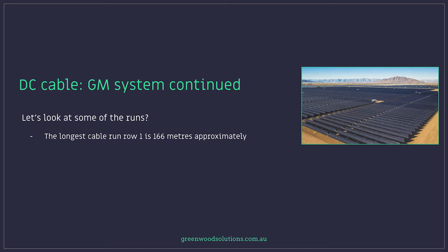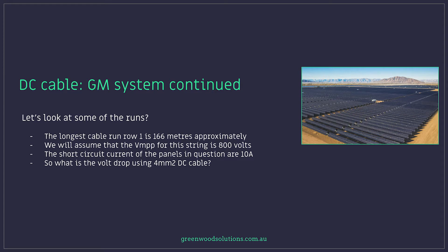The longest cable run, row 1, is 166 meters approximately. We will assume that the voltage maximum power point for this string is 800 and the short circuit current of the panels in question are 10 amps. So what is the volt drop using 4mm squared DC cable?